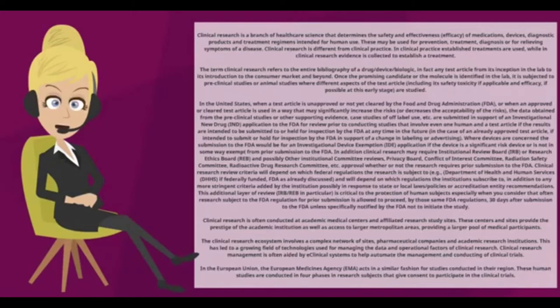Where devices are concerned, the submission to the FDA would be for an Investigational Device Exemption (IDE) application, if the device is a significant risk device or is not otherwise exempt from prior submission to the FDA. In addition, clinical research may require Institutional Review Board (IRB) or Research Ethics Board (REB) approval, and possibly other institutional committee reviews — such as a privacy board, conflict of interest committee, radiation safety committee, or radioactive drug research committee.